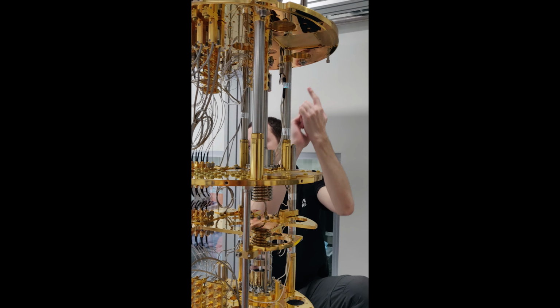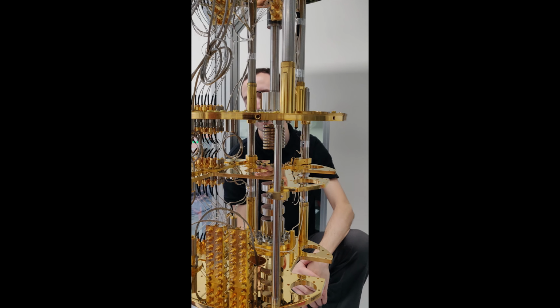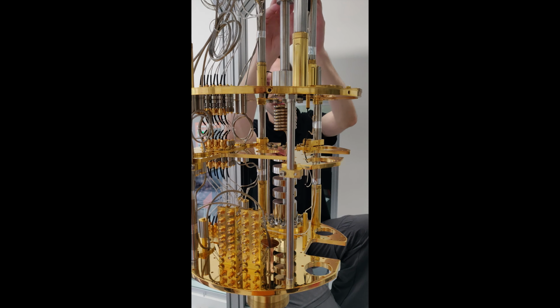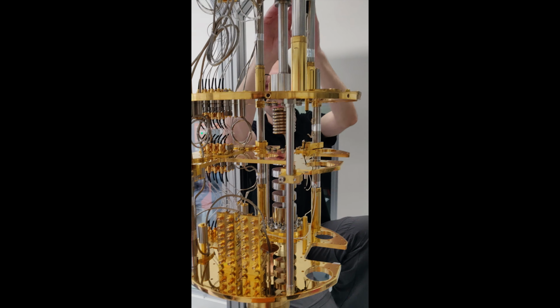We even need to heat it, because pumping it out cools the still so much that it doesn't evaporate anymore. So there's a still heater, and we apply heat to this plate, keeping it at 800 millikelvin, to achieve cooling here. We heat it up in order to achieve cooling, because we evaporate helium-3 from there, decreasing its amount, so helium-3 must pass through the phase boundary. That's the quantum phenomenon responsible for continuous operation of the fridge. It goes down, gets pumped out here, must pass through the phase boundary, and that's how it becomes cold - this coldness is transferred to your experiment.